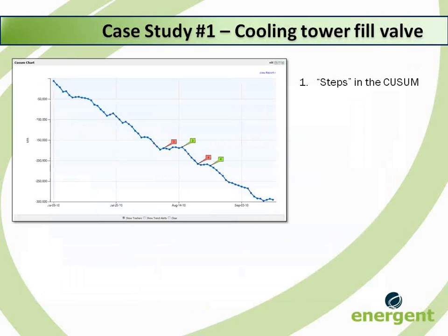The steps in the CUSUM were caused during times when the operator was not at the hospital. Because the fill valve was broken, the operator would manually fill the cooling tower to the optimum level, ensuring the pump worked effectively. When the operator was not there, the cooling tower water level would drop below the optimum level, and the pump would have to work much harder to circulate the water through the cooling system. This caused an increase in electricity being used by the pump.